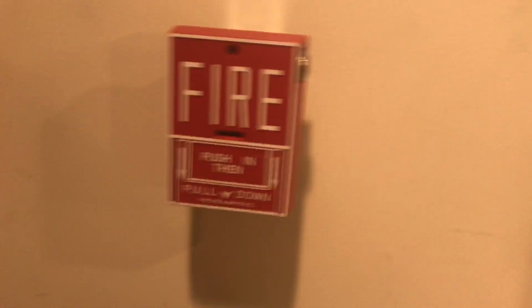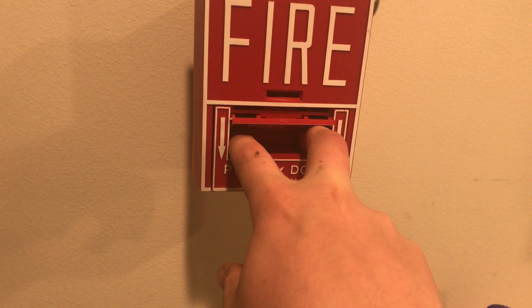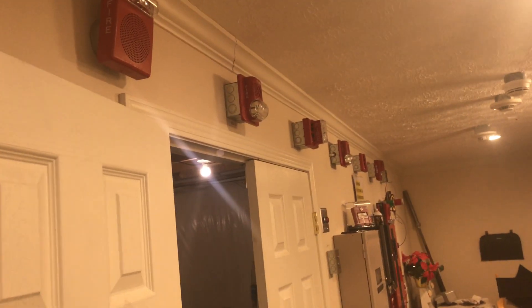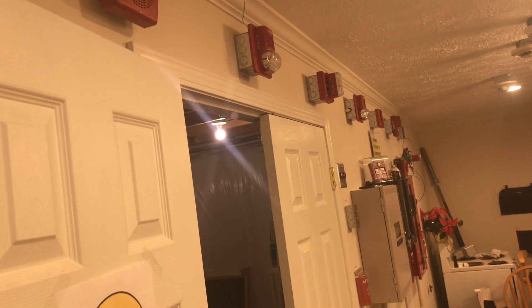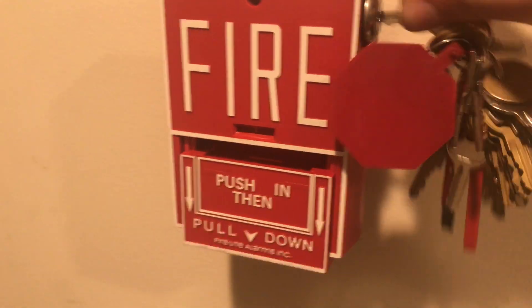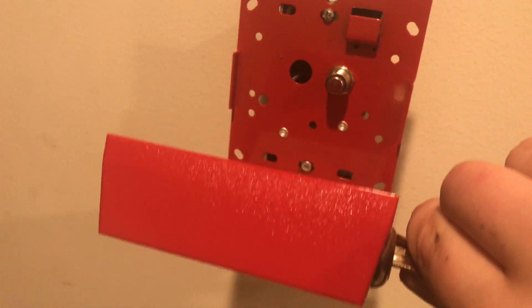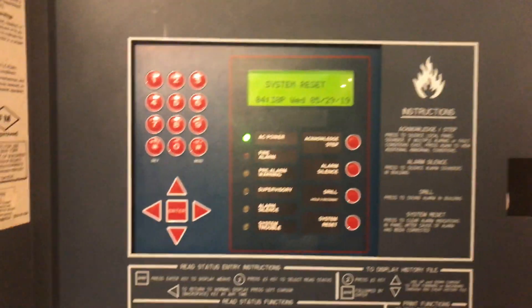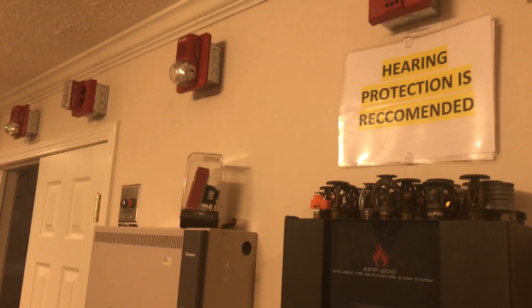Here we go — push and pull on the BG-10L. To reset this one, we put our key in, turn it, and everything pops back up, then close it. Note that holding the reset button makes coded devices go continuous while the panel is resetting — that's why that happened.